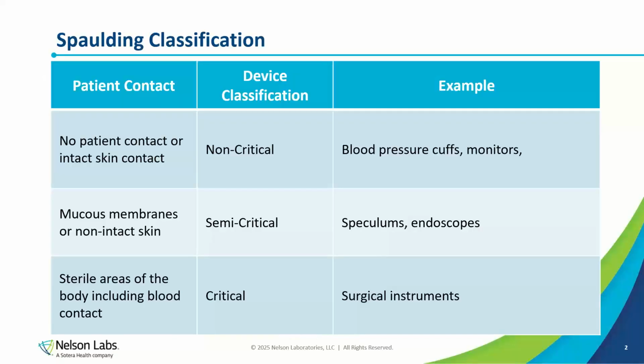And again, to reiterate and go over, reusable medical devices can be categorized into 3 different classifications using the Spaulding Classification. This classification is really just based on how the device interacts with the patient, and it will let you know what reprocessing instructions are needed for that particular device. Those devices that are either non-patient contacting or will contact intact skin are classified as non-critical devices. These are items like blood pressure cuffs, monitors, and carts, things that have low risk associated with them, and really only need to go through cleaning, and then in most cases either low level or intermediate level disinfection.